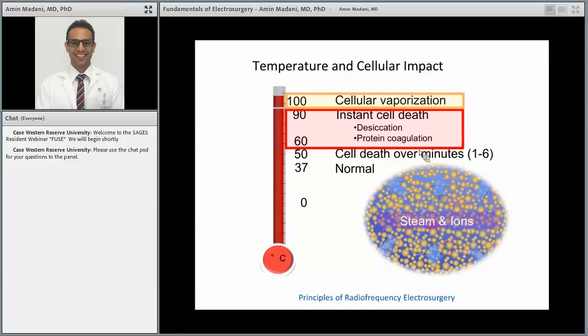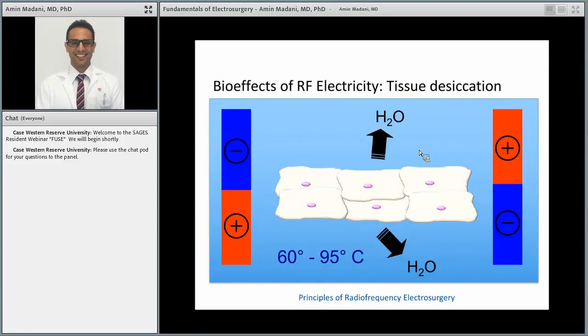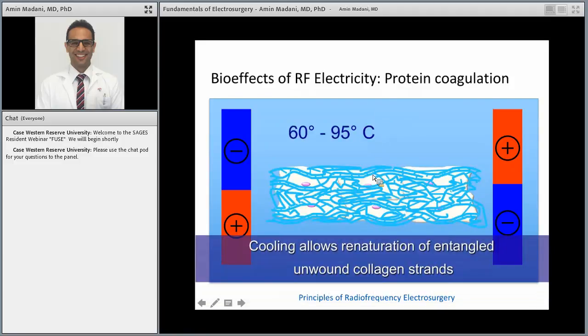To demonstrate that again, at 60 to 95 degrees Celsius, you get tissue desiccation. The cell membrane breaks down, water evaporates, and the cell begins to shrink. Similarly, you get denaturation of the proteins, and when it cools down, it reforms, but in a haphazard manner, not in its original shape. So you get this white coagulum that forms, and this is called desiccation and coagulation, in the 60 to 95 degrees Celsius range.